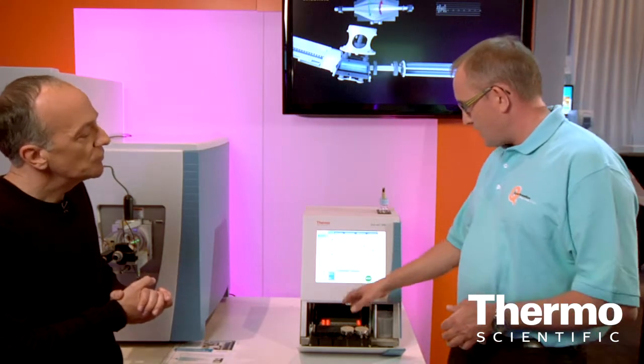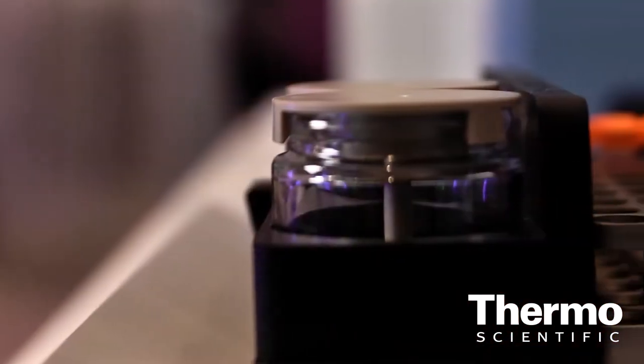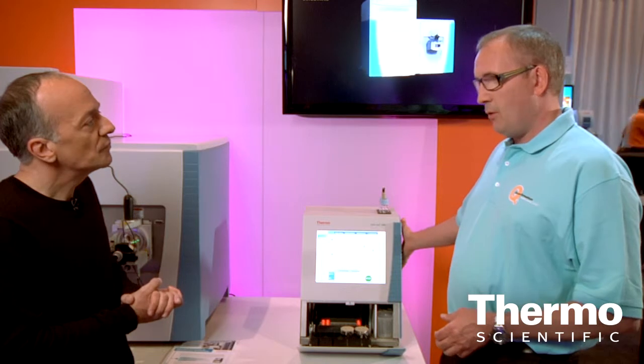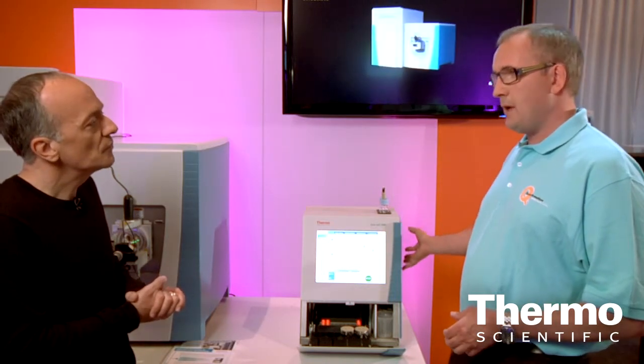This unit is a complete integrated system. It has a cooled auto-sampler, currently equipped with vials, and you can also use micro-titer plates — even high-capacity micro-titer plates. Inside there's a complete computer with a touch-screen interface, along with all the NanoFlow pumps, switching valves, tubing, and flow sensors that enable the system to work with the high precision required for these types of analyses.